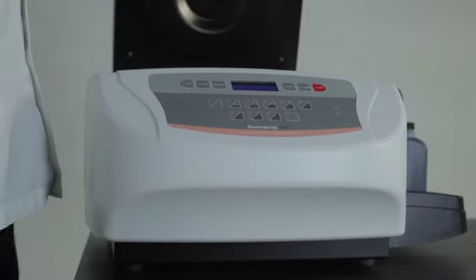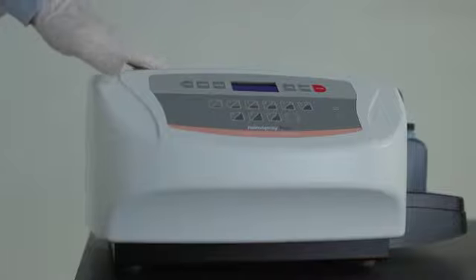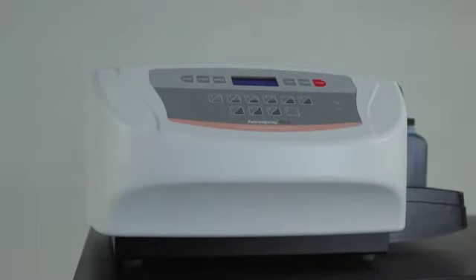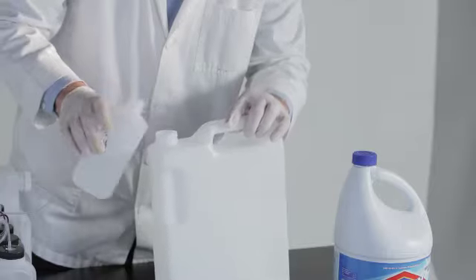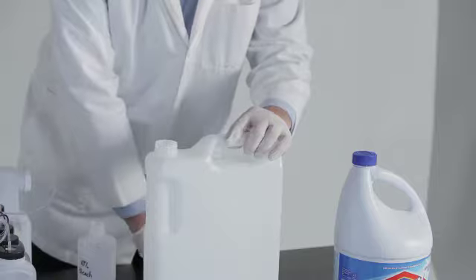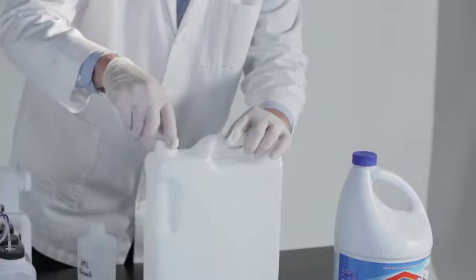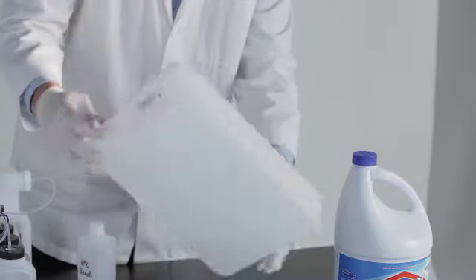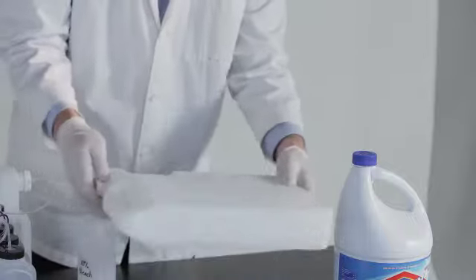Special preventive maintenance includes a monthly B-line flush. Instructions for performing the B-line flush are in the applications manual and the preventive maintenance chart. The flush is semi-automated with the firmware. The 5-liter container used on the D-line should be cleaned with 10% bleach once per month to prevent bacterial contamination of the water.